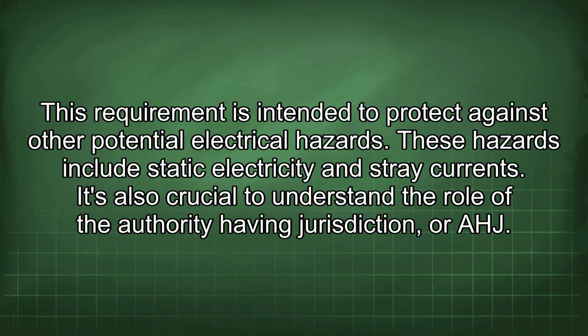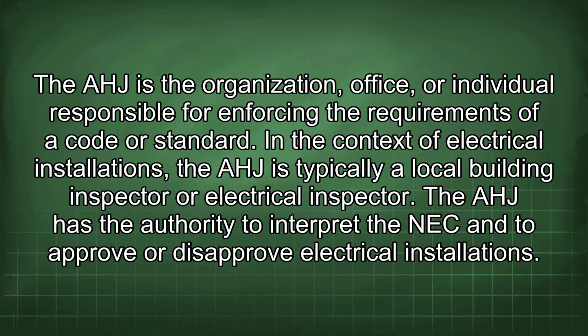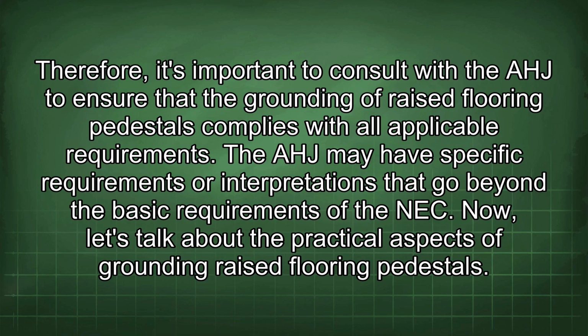It's also crucial to understand the role of the authority having jurisdiction, or AHJ. The AHJ is the organization, office, or individual responsible for enforcing the requirements of a code or standard. In the context of electrical installations, the AHJ is typically a local building inspector or electrical inspector. The AHJ has the authority to interpret the NEC and to approve or disapprove electrical installations. Therefore, it's important to consult with the AHJ to ensure that the grounding of raised flooring pedestals complies with all applicable requirements. The AHJ may have specific requirements or interpretations that go beyond the basic requirements of the NEC.